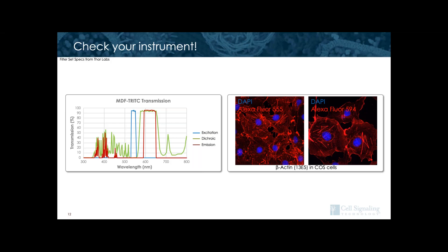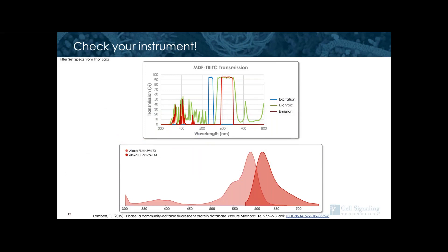Here I'm showing two fluorophores that are both part of the red spectrum but are spectrally distinct. We capture images in grayscale and then pseudocolor to what we think best represents the fluorophore — in this case, both are red. The excitation and emission curves for Alexa Fluor 594 show that using this TRITC filter cube significantly diminishes the wavelength of light that can excite your fluorophore. Alexa Fluor 594 would be best excited in the 600 nanometer range; however, the filter cube only supplies light between 530 and 560 nanometers, significantly diminishing signal intensity.